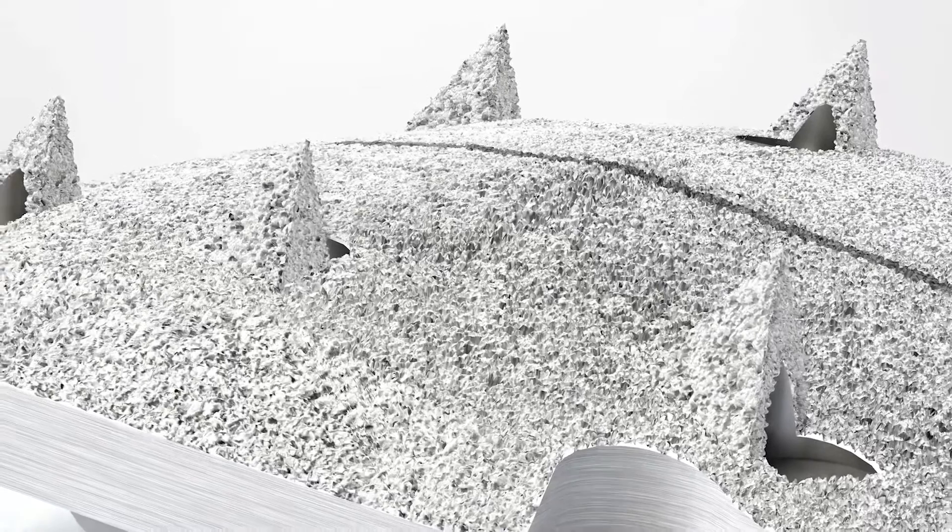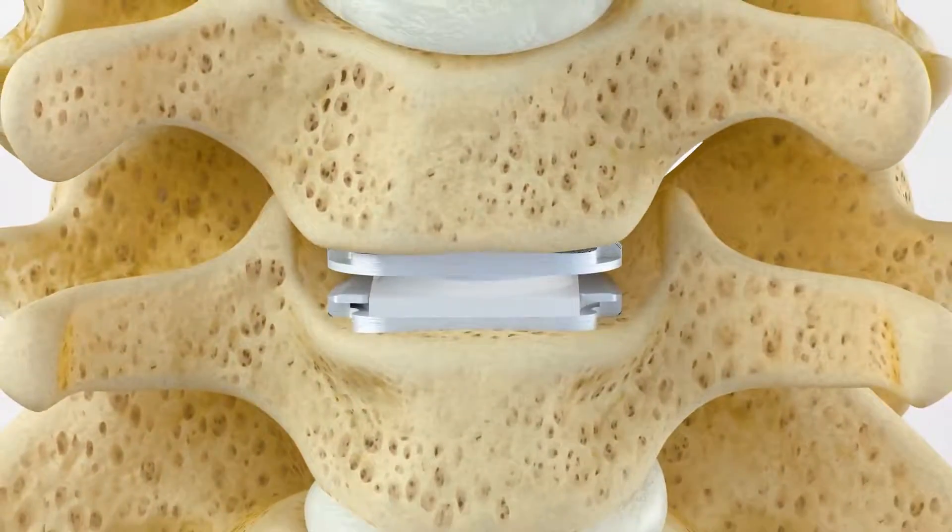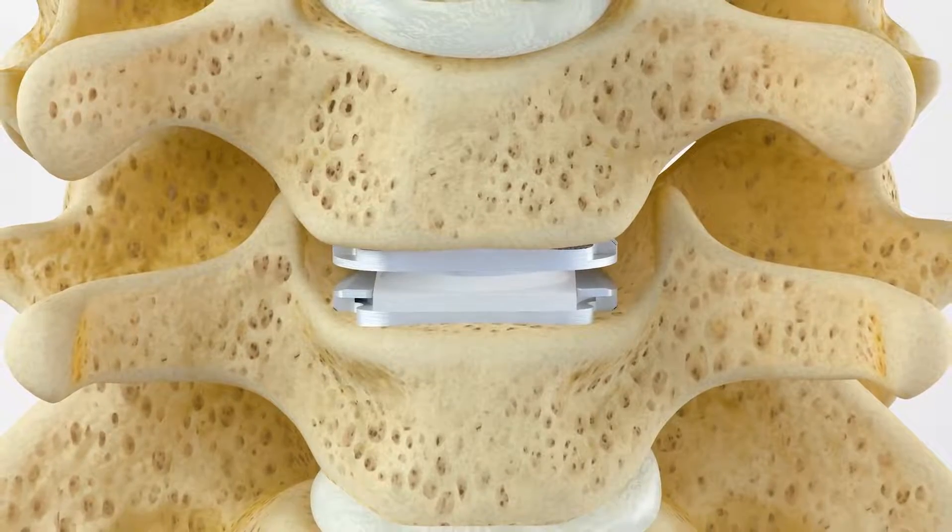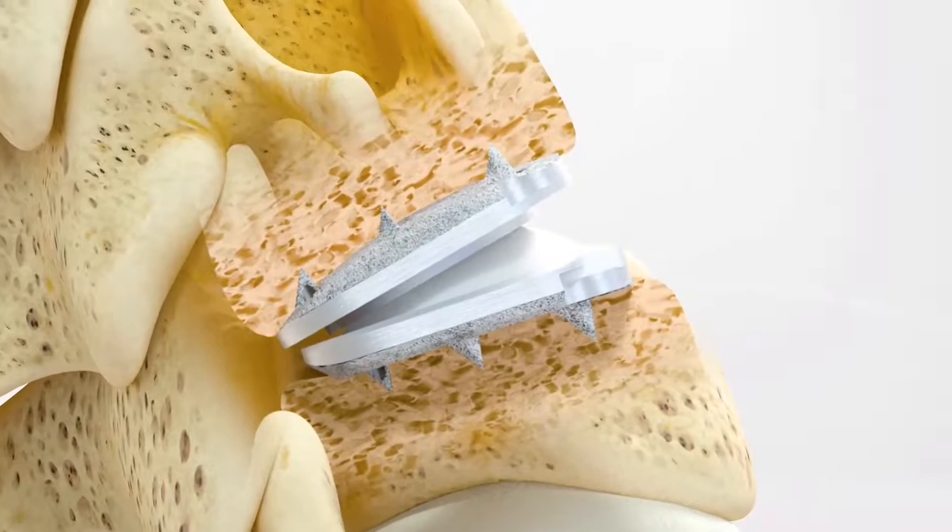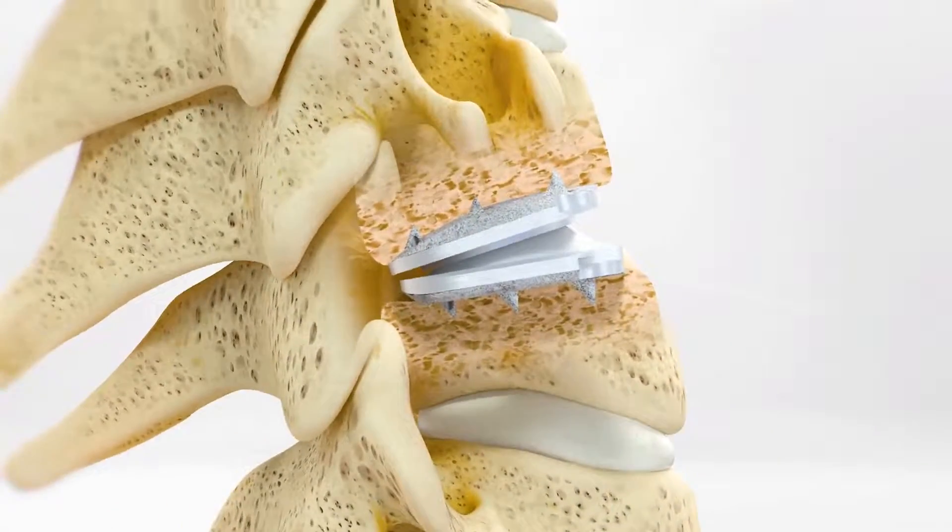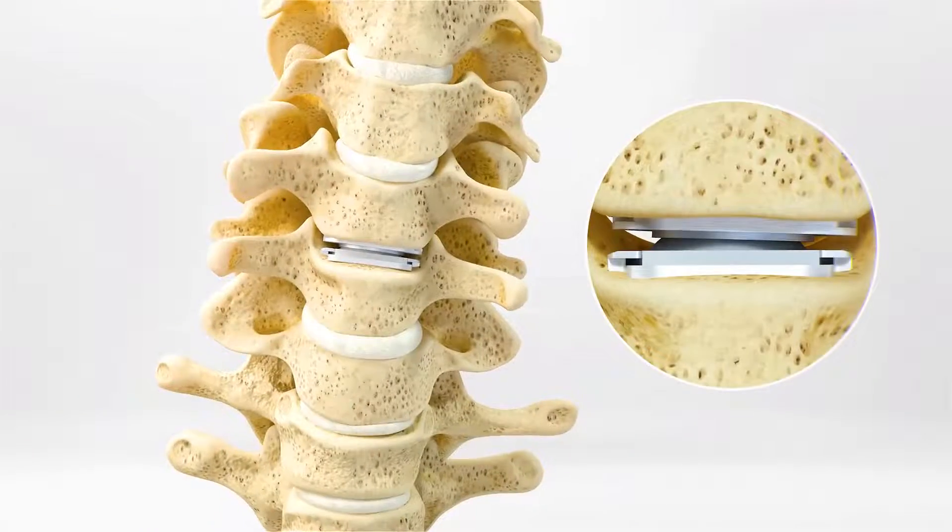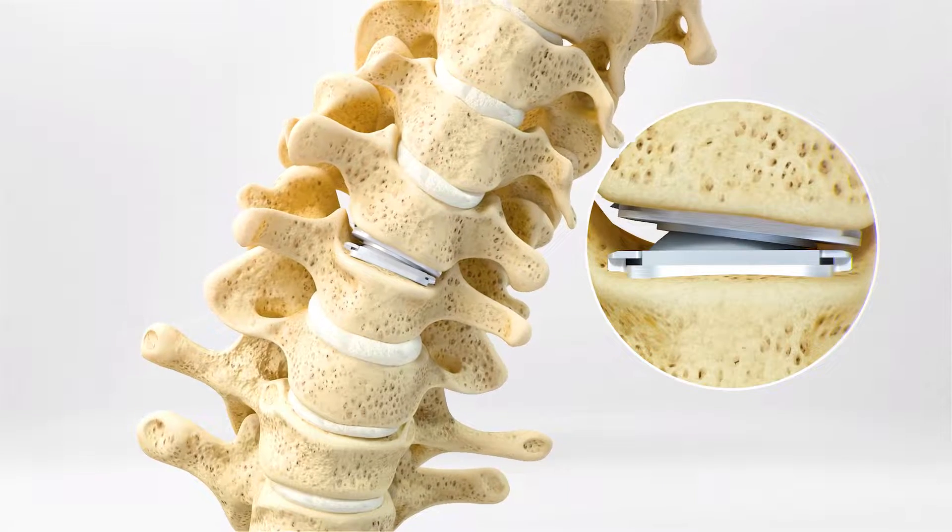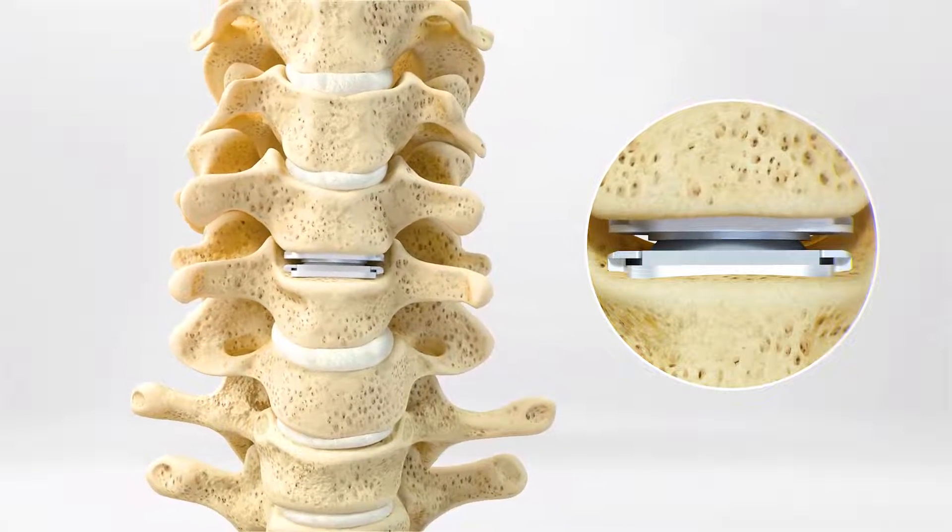The ProDiscC Vivo Implant is secured to the vertebral bodies above and below the disc space with a convex superior end plate and six spikes on the superior and inferior end plates. The implant components work together with surrounding spinal structures to provide stability and function. The ProDiscC Vivo is a zero-profile implant that does not contact soft tissue structures after implantation.